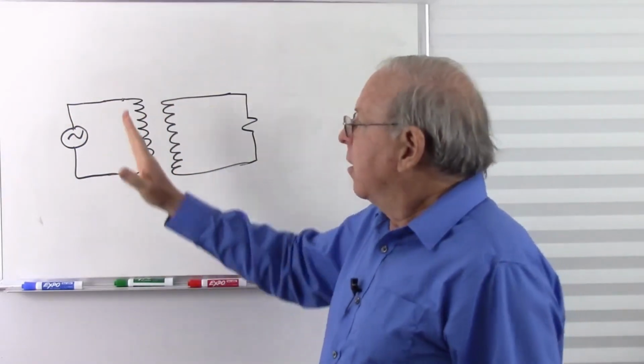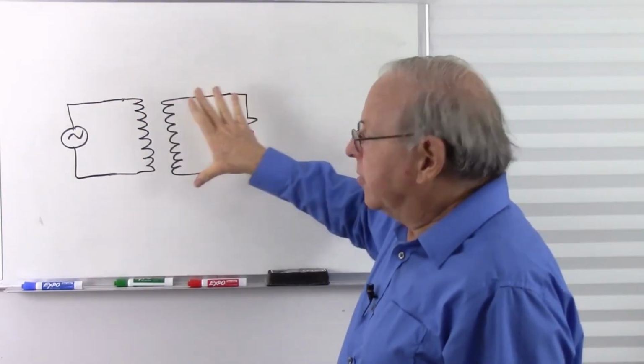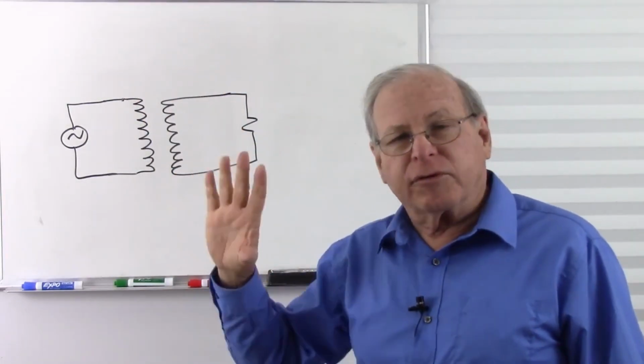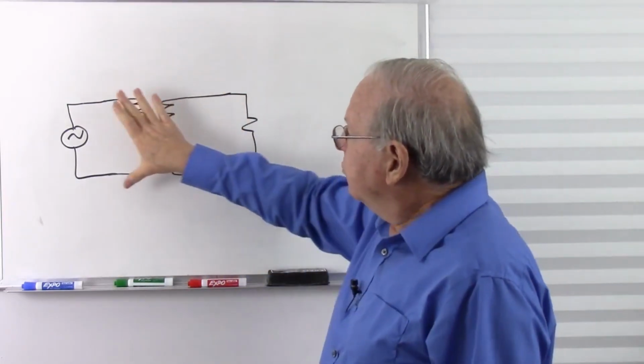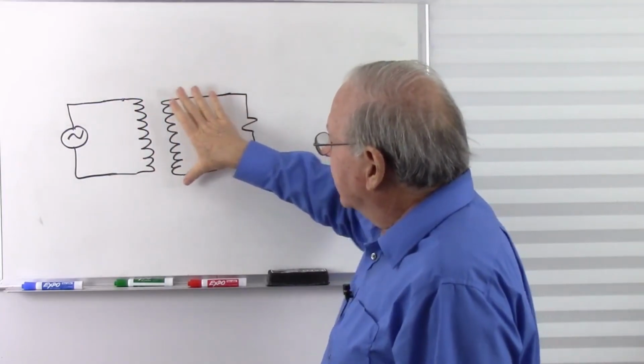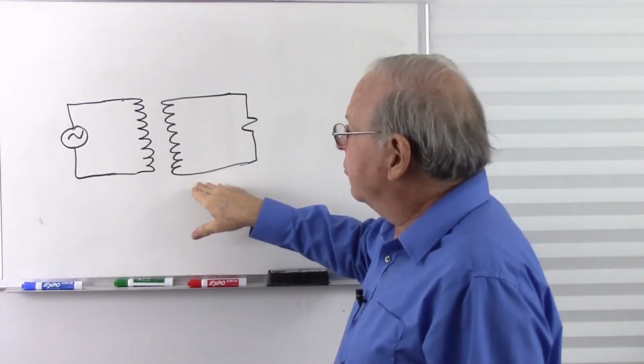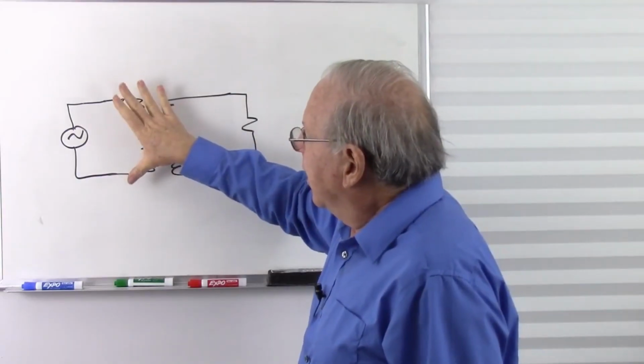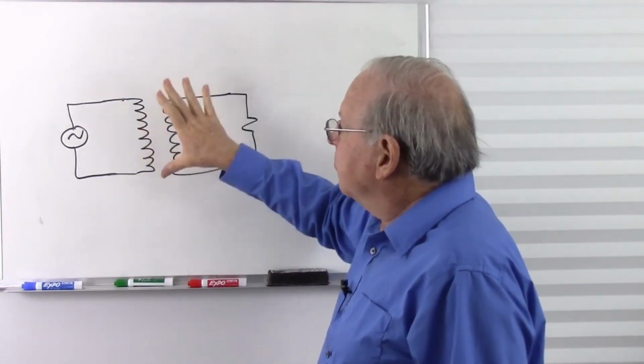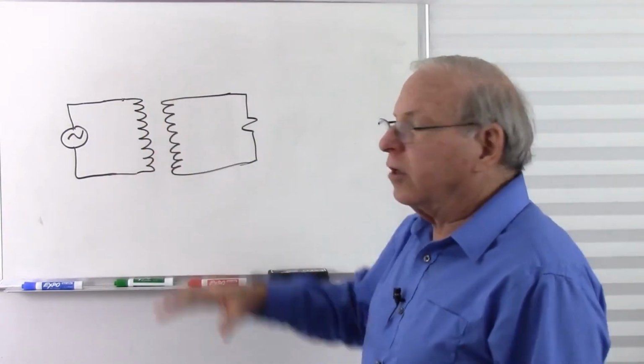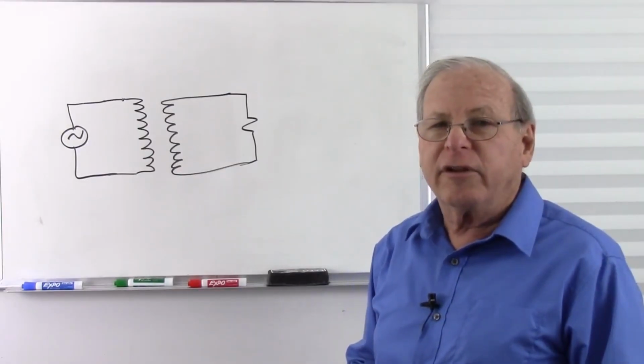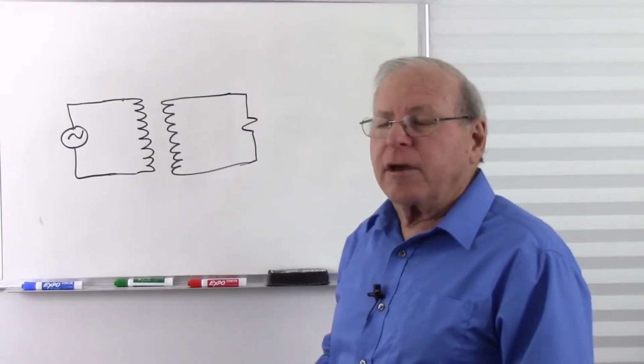So all transformers, except for auto transformers, which I will mention later down the road, all transformers will isolate us electrically. We don't have a galvanic connection. An isolation transformer will also be optimized to give us good high voltage insulation to reduce leakage currents. And another thing we want to minimize is capacitance.